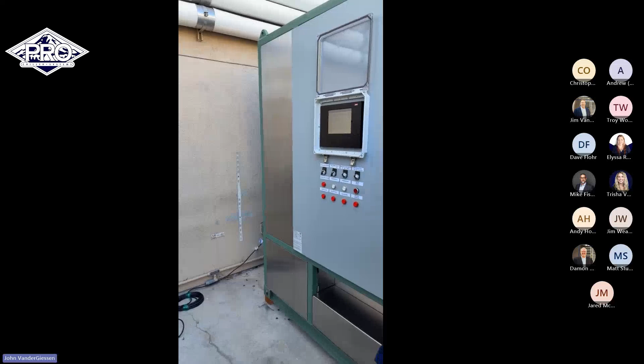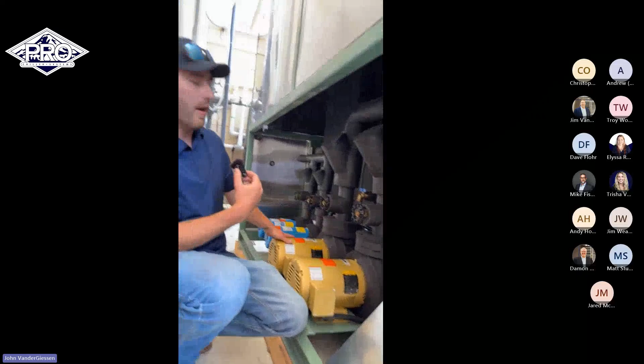On the back side over here is the pumps. So this is the fluid flow to the chiller evaporator, as well as the process pump, which goes inside and feeds his process loop and cools down the beer and tank. Process pumps, you have a primary and a backup. The primary pump is on a VFD drive, which is right here. So it's controlled based off of a pressure set point. So we're controlling it to 25 PSI is what that pump is ramping up to.